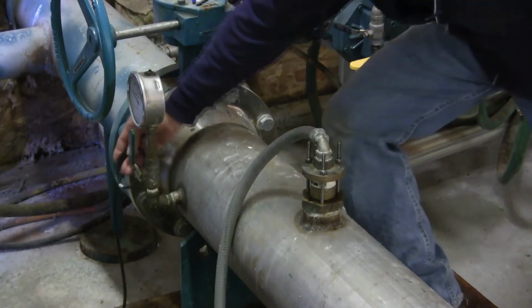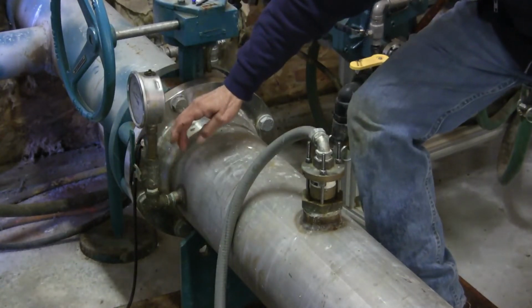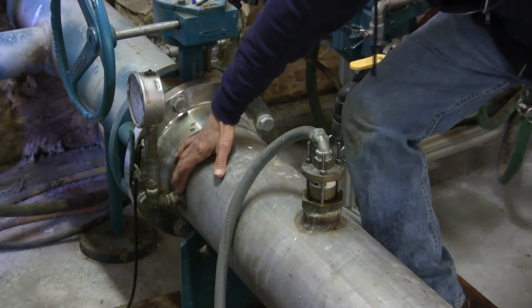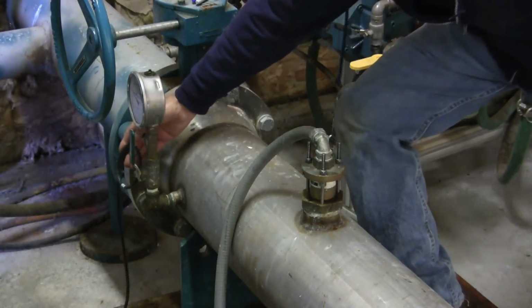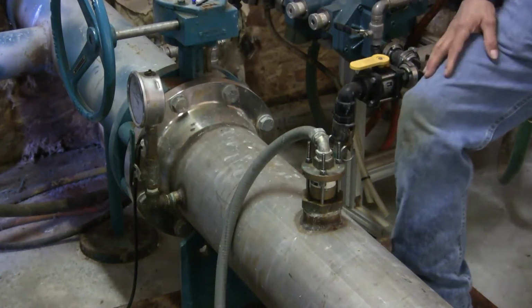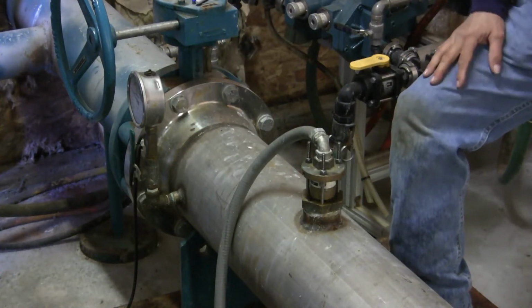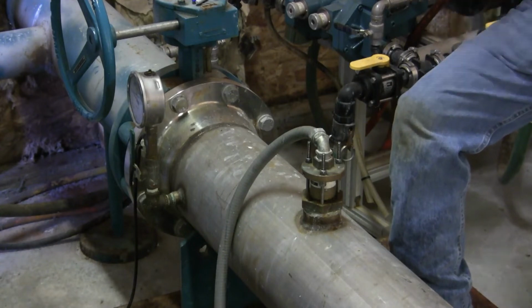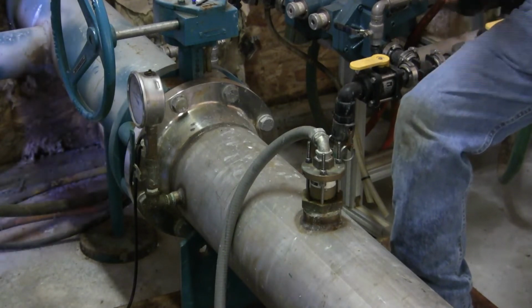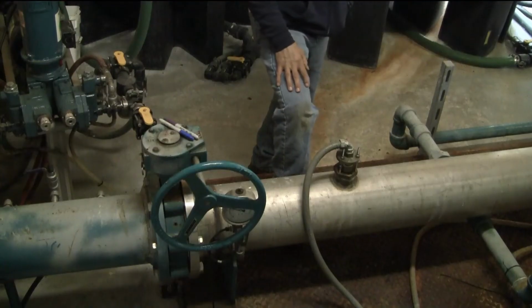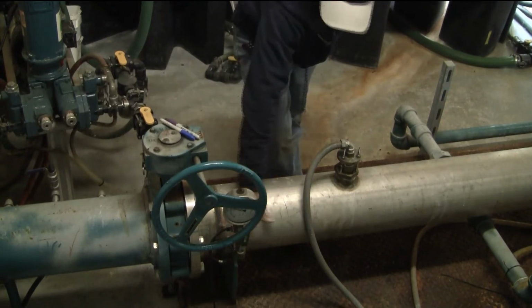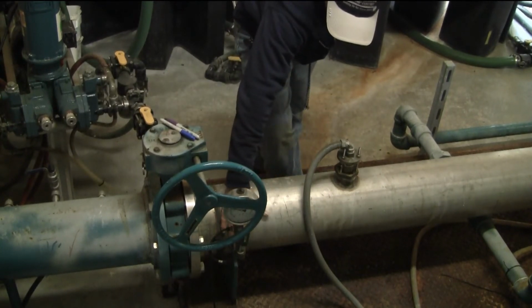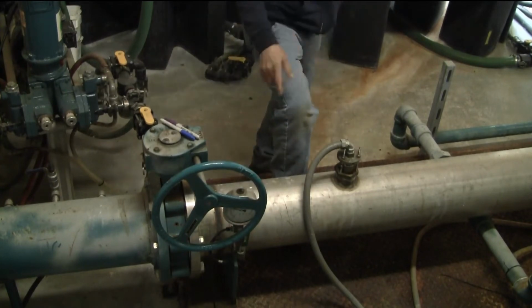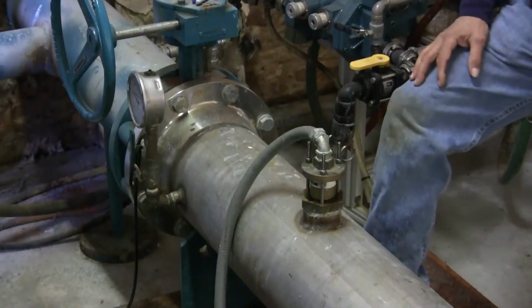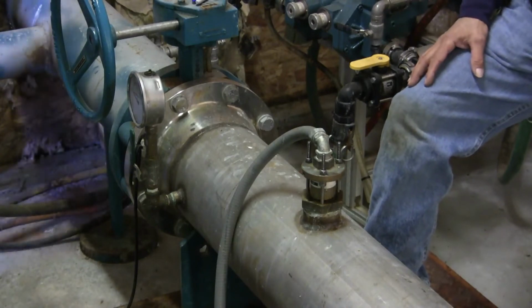These gauges, the small tubes. This little 1/2-inch port feeds the gauge. More importantly, this small tube, which runs to a pressure transducer, that's what the panel sees. When it's running the station, you need to have a pressure reading, so the pump station knows what to do. I've seen it already. I've taken the gauge, everything off, and that port is completely clogged, and you're not getting accurate readings.